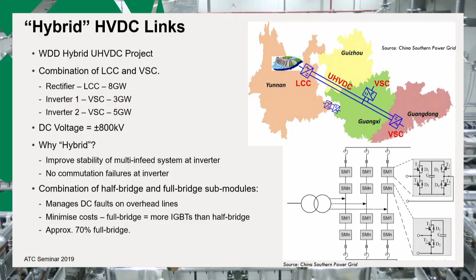Just quickly, half bridge, you can't control the DC current during a fault. Full bridge, you can. They've worked out that all the modules don't need to be full bridge. The disadvantage of full bridge is it's twice the number of IGBTs than a half bridge, so it's more expensive and it'll have more losses.